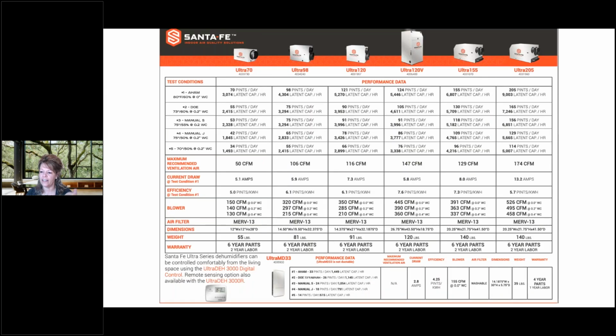And then in the handout section of the webinar here, I did upload this piece of literature. It is also on our website, but we break down our latent capacities per hour for each one of our dehumidifiers at the different conditions. So we have AHAM, which is 80 degrees, 60% relative humidity, and then the new DOE, which is 73 degrees, 60%. Manual S is 75 and 55, Manual J is 75 and 50.